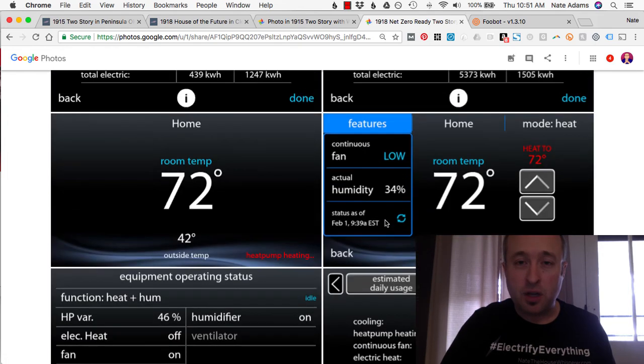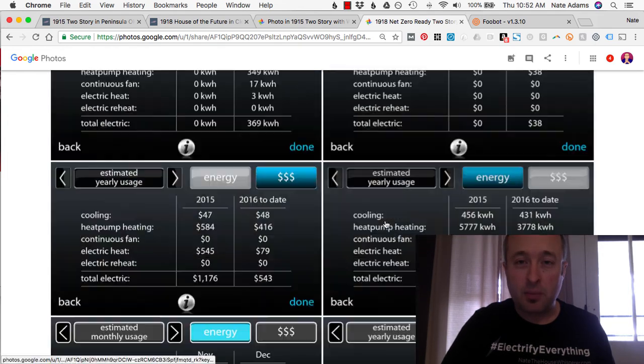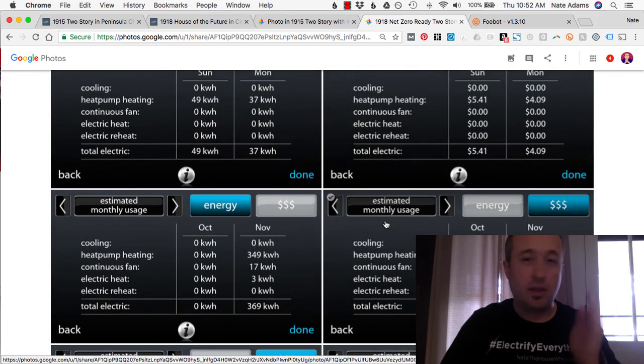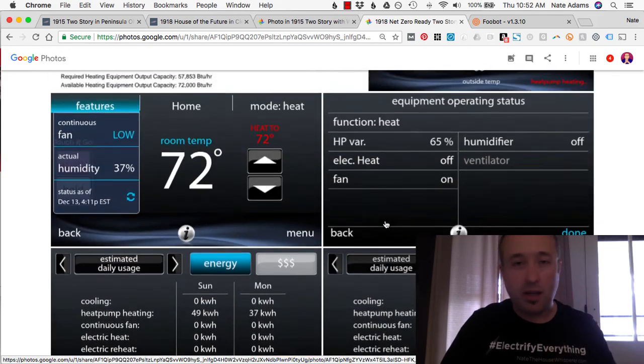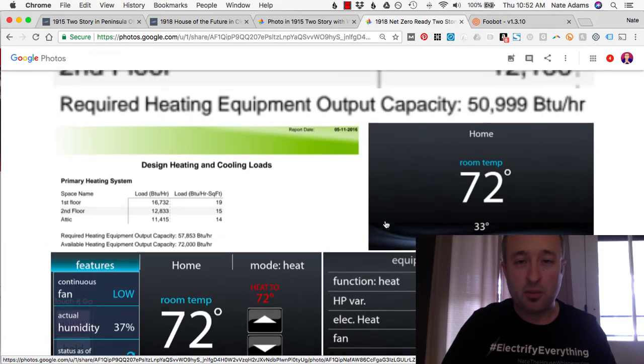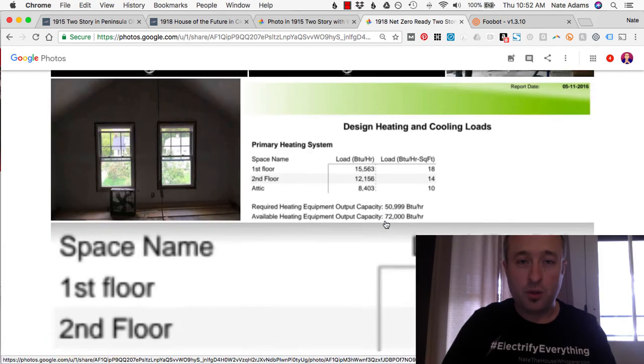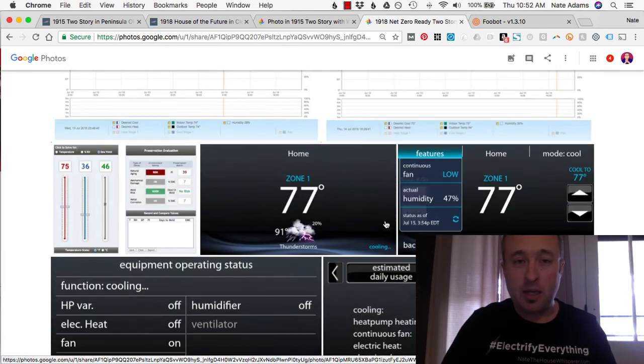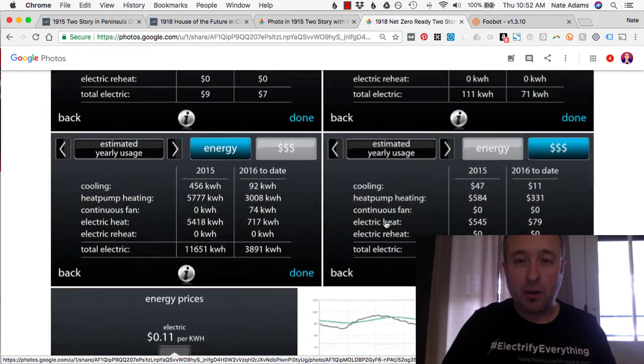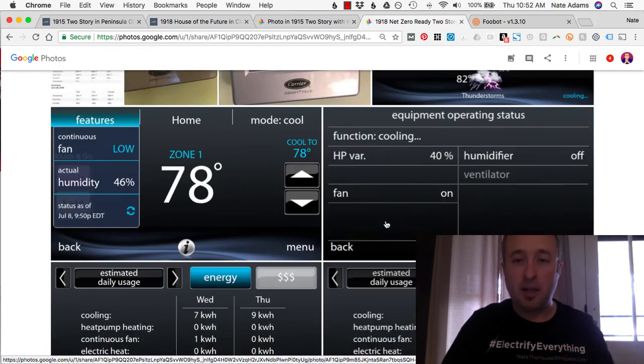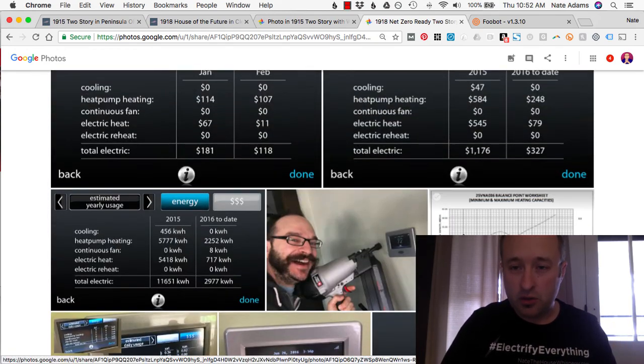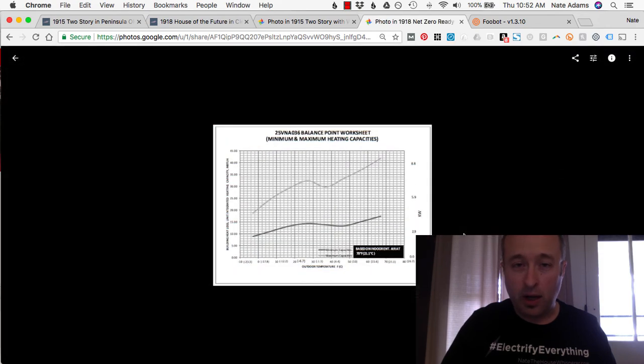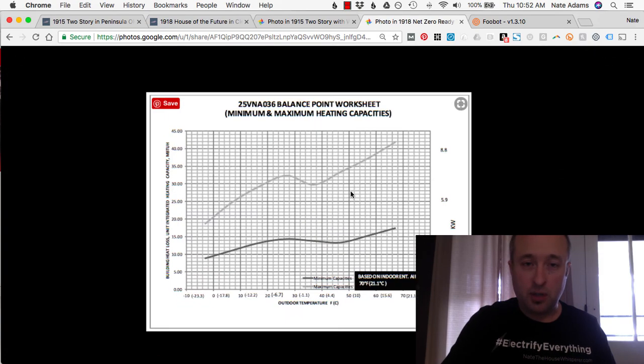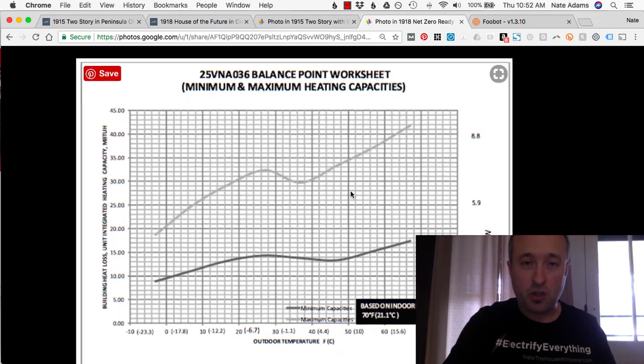In the case of John's house, this has a heat pump, and where a furnace puts out the same amount of heat all the time, it doesn't really matter what the temperature outside is, you're in good shape. Heat pumps lose power, they lose heating capacity as it gets cold outside. So this is where I have to look instead, at what's called a balance point worksheet.